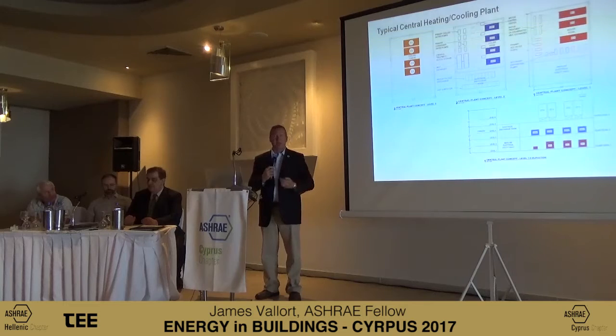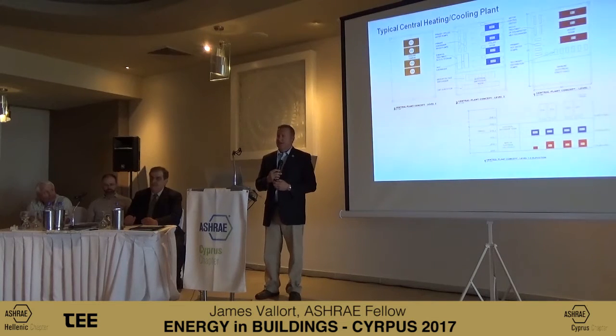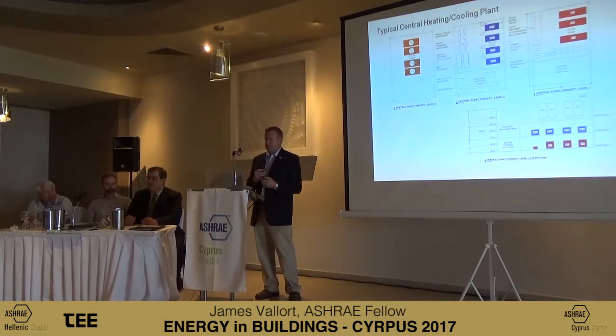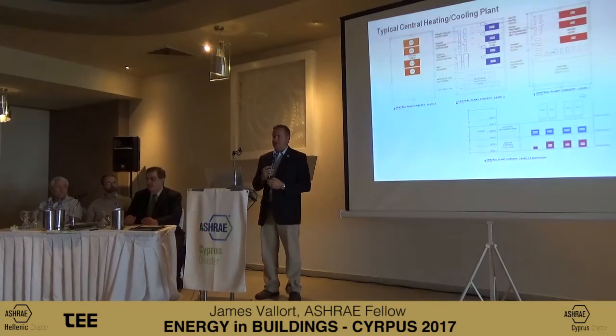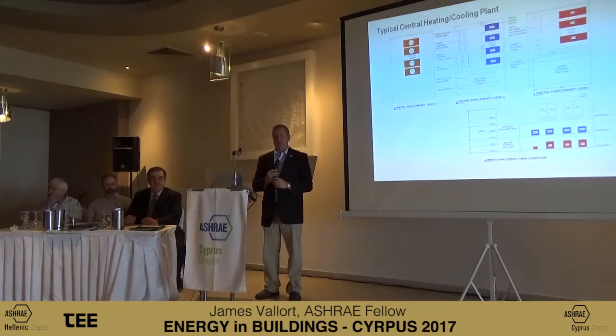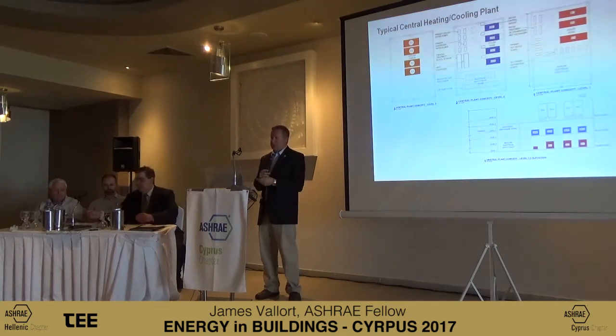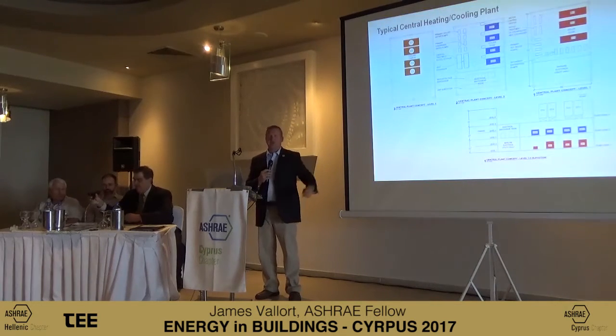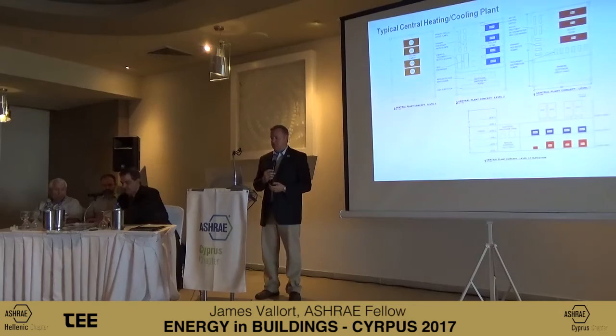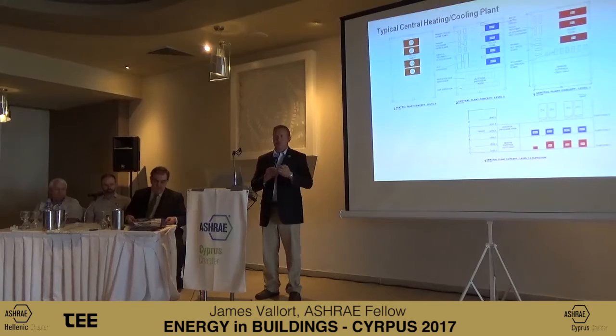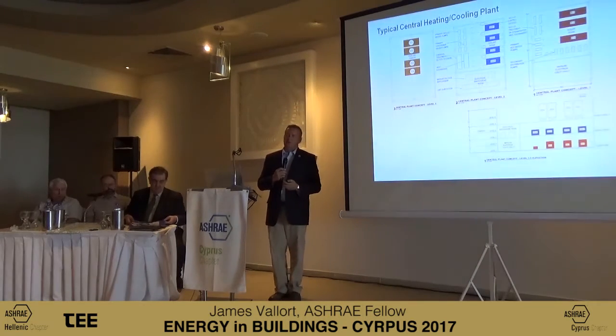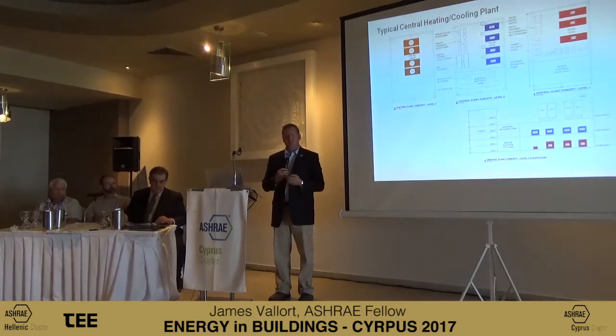We're going to walk through a scenario where we select a central chilled water plant scheme. I'll lay a framework for a large campus or hospital. Hospitals are unique because they often have five or six different generations of building. The basic building will have a heat rejection section for cooling towers, a chiller room, boiler room, and an electrical room. One of the key things is understanding your limitations — in certain parts of the world you may not have enough electrical power.